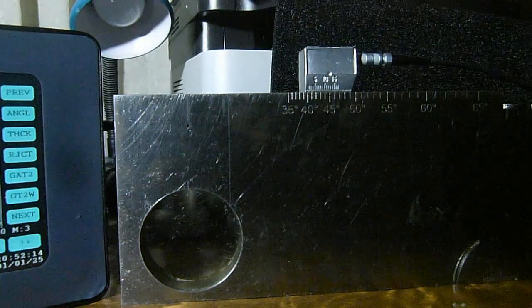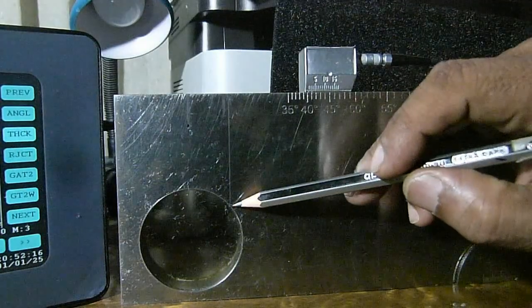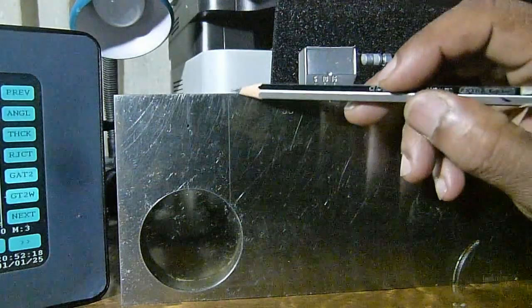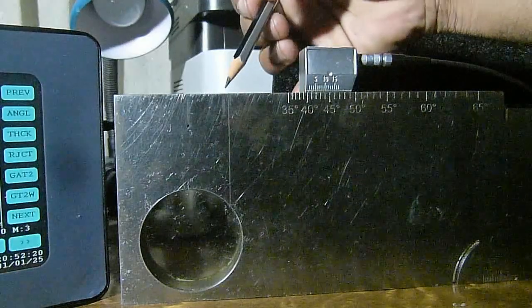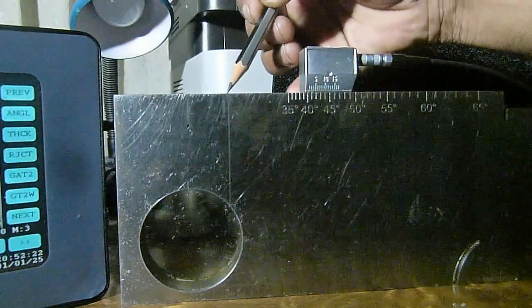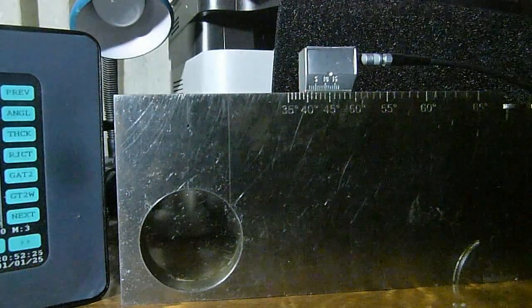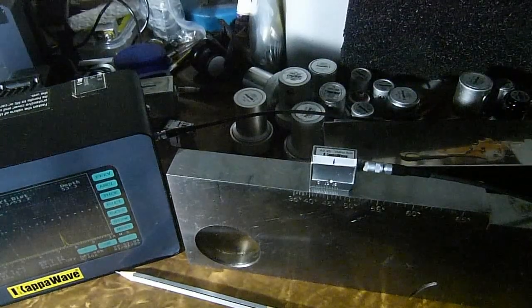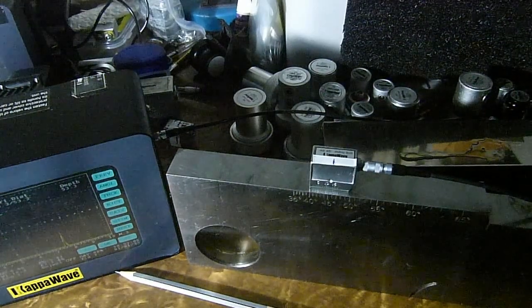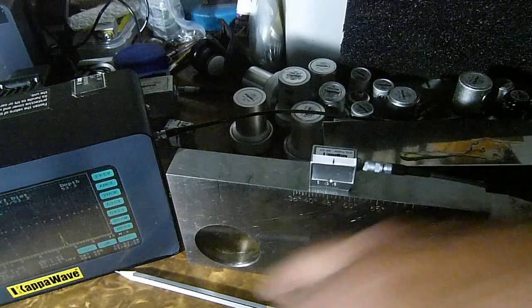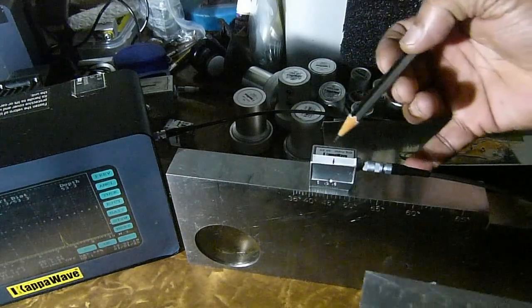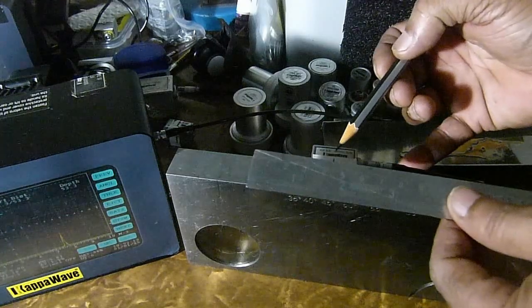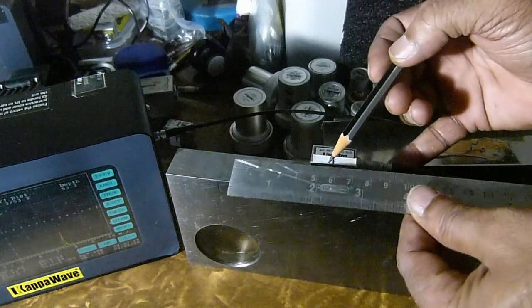If the surface distance is measured from the center of the probe or from the index point, then it would be 53 mm. If you want to mark the location of a reflector, this can be used. If you have access to the top marking of the probe, then the tape measure may be used to correctly mark that 53 mm on the material.